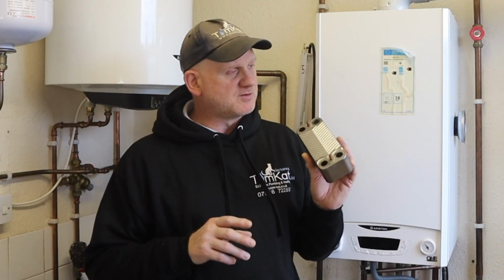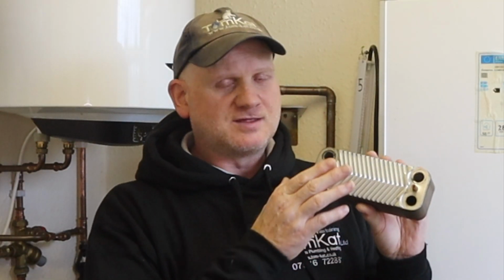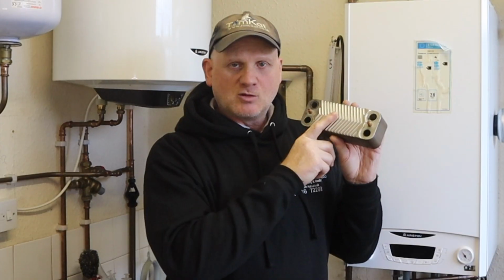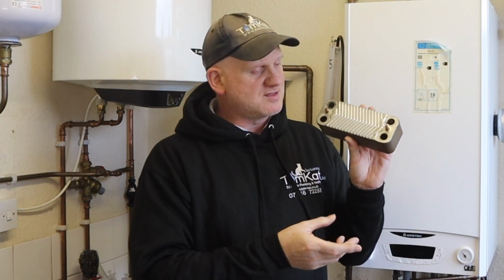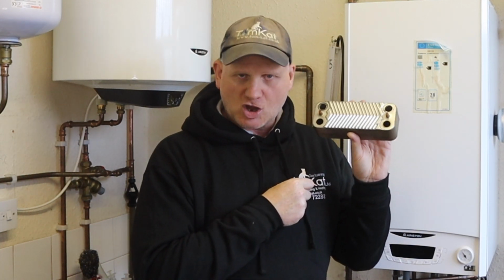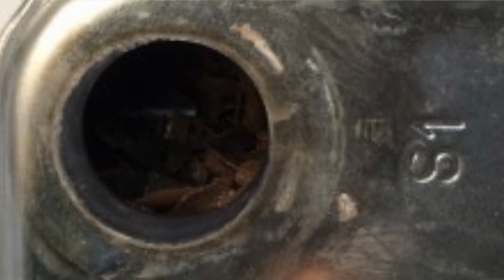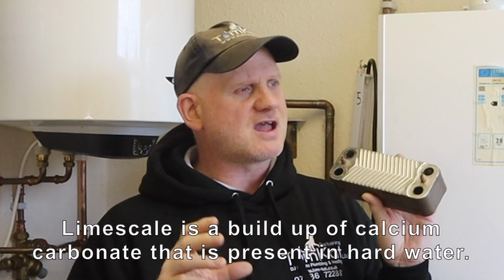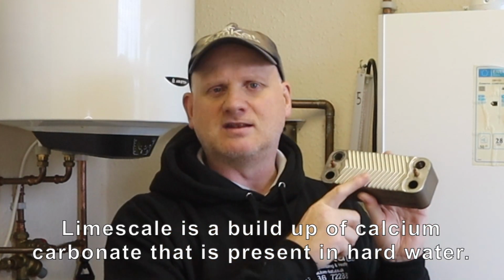Now, one of the other parts of the boiler we need to protect from sludge is our plate-to-plate heat exchanger. This is what takes the heat from the main heat exchanger and turns the cold water coming into the boiler into your hot water going out your taps. So as well as protecting your radiators and your central heating system, we also need to protect this little thing if you've got a combi boiler from the sludge and magnetite also. But one of the things we don't think about here in the northwest about protecting this from is limescale. Now, there's a lot of engineers out there who do have to consider protecting the plate-to-plate heat exchanger from limescale, and also the main heat exchanger.